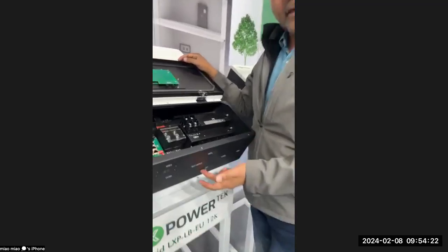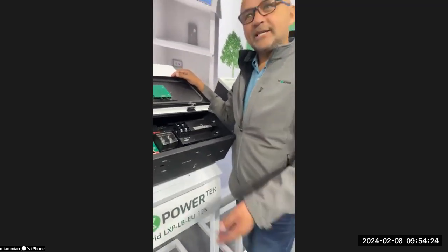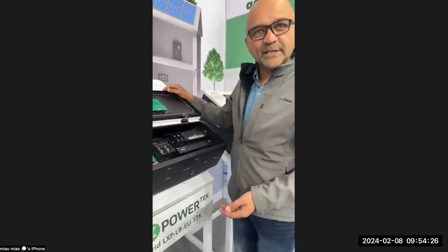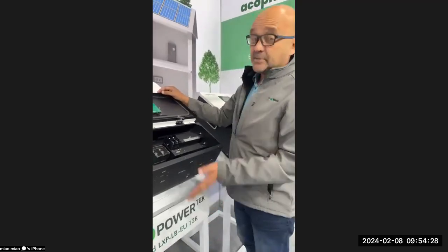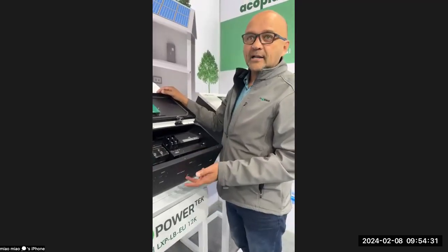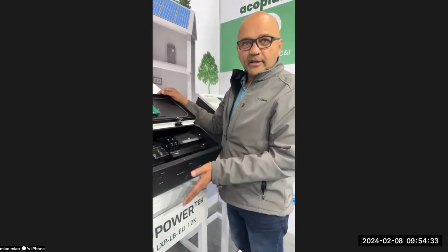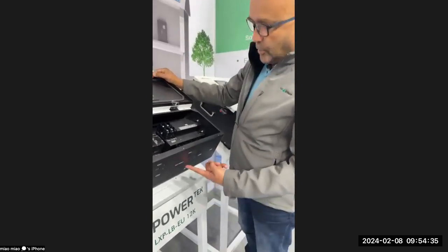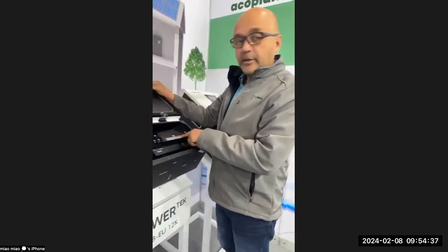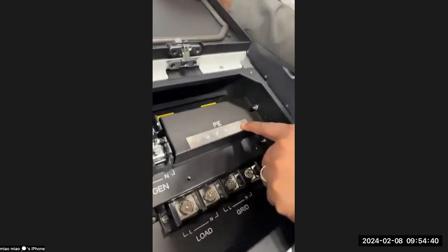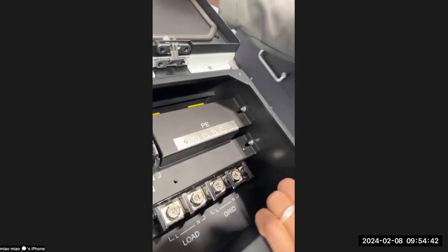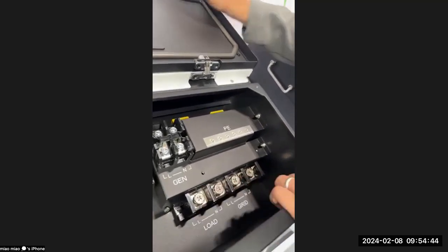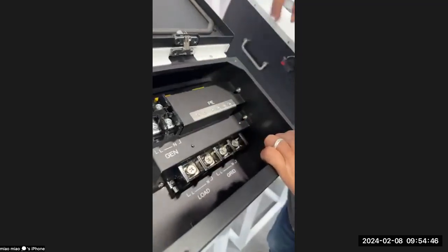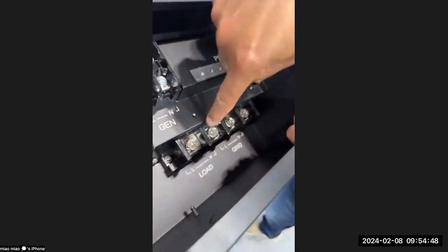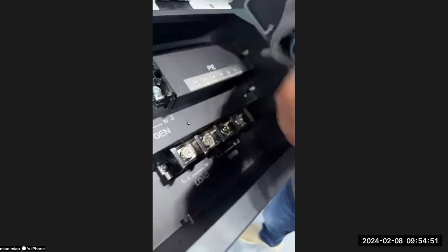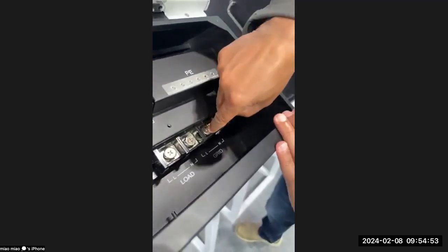Okay. So you're earthing your battery, chassis, everything that's to do with your installation where it requires earthing, do it. But especially on the machines, we need to do that because we can create damage to the machines if the earthing is not done correctly. So we've got an earthing point there for the chassis. We've also got a common earthing point inside the machine here, right? And then on here, we have quite beefy terminals on the 12 as well as the 10, which is for your load and your grid supply, right?